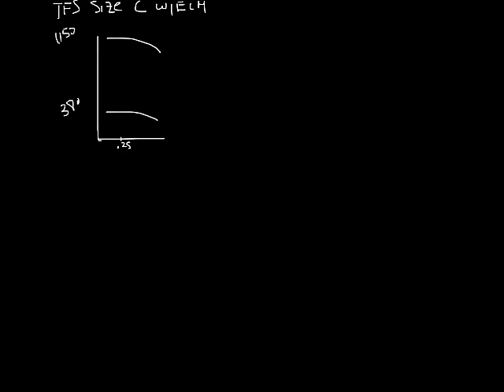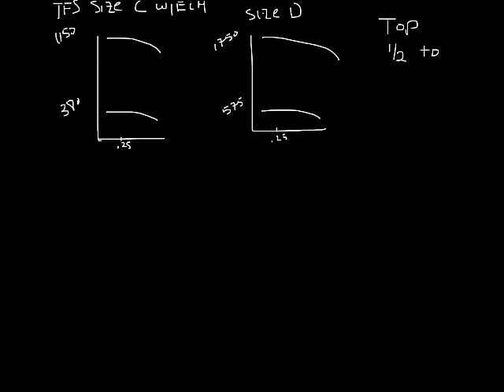If you look at several size fan boxes, you'll see that there's some overlap in the fan curves. For instance, a TFS casing size D with an ECM motor has a minimum CFM about 575 CFM at 0.25 and a maximum about 1750 CFM. So how do you know which one of these two to select? It's best to select in the top half to third of the fan curve, because as you turn down the box, the motor will become less efficient. My example is an ECM motor, so it stays pretty efficient throughout the entire operating range, but it still will become less efficient as you turn it down.